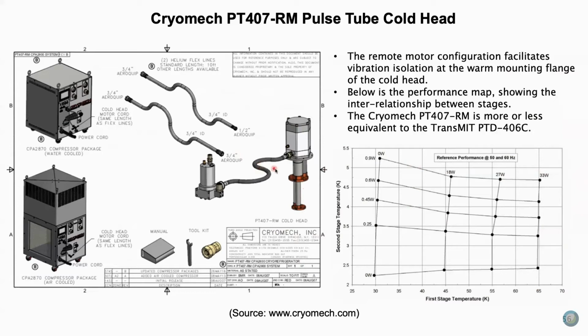Here is an example of a pulse tube. This is the pulse tube cold head here. There's a motor assembly that controls a valve that converts the unidirectional flow in these flex lines to pulsating flow. And those connect the cold head to the compressor. So this is actually the same compressor that I showed you before that is installed on SOFIA. Two of them are installed.